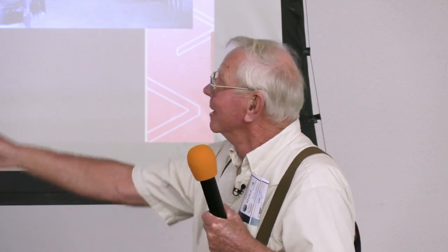If the train wrecked, or if the power line came down and went to ground, and it short-circuited that 3,400-volt, or 3,400-amp service given to that train, it would trip that breaker like the breaker in your house. You'd see a spark in the breaker, like if you pulled a plug out while running a skill saw instead of switching it off, you'd draw an arc. So the arc that comes out of there can go two stories high in that building.